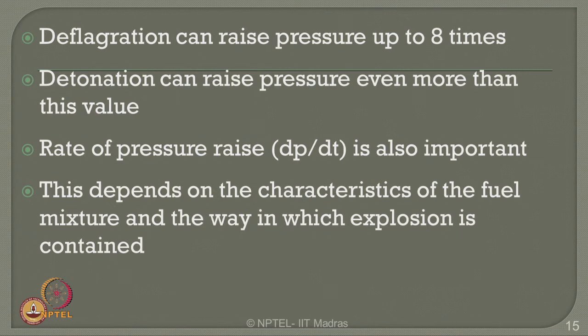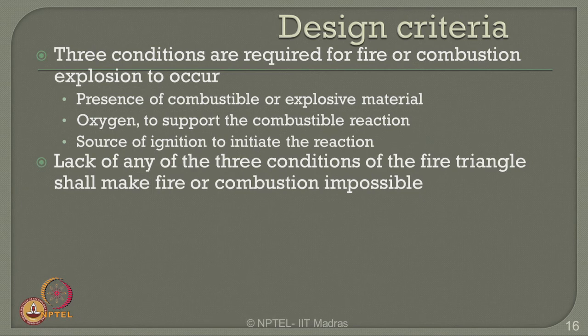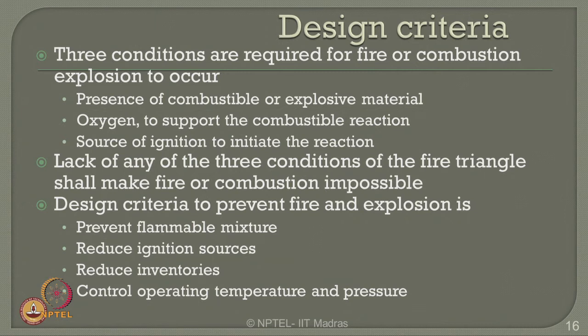This depends on the characteristics of the fuel mixture and the way in which the explosion is contained. Now let us look into design criteria for containing or confining explosions. Three conditions are required for fire or combustion explosion: presence of combustible material, oxygen to support the reaction, and a source of ignition. Lack of any one of these three conditions makes fire or combustion impossible. Design criteria to prevent fire and explosion: prevent flammable mixture, reduce ignition sources, reduce inventories which can cause ignition, and control operating temperature and pressure.